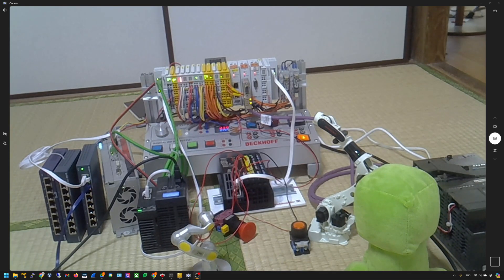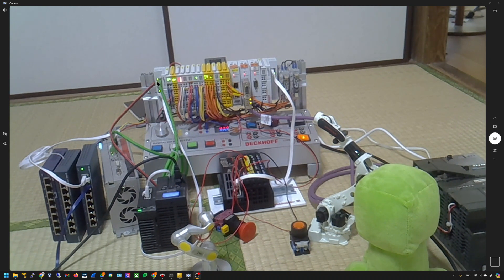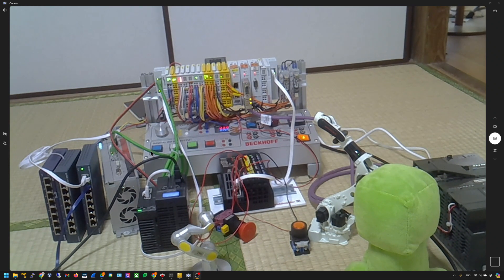Here is the real hardware configuration I'm using this time. The main part is the Beckhoff device — here is the EK1101 EtherCAT coupler. You can see a white cable connecting to my KEYENCE PLC KV-8000, and next to the KV-8000 there is the KEYENCE module KV-XLE02 — this is the module I'm using this time. It will act as the EtherCAT slave, which is why the white cable connects to this module. On the other side, the Beckhoff IPC has a green cable connecting to the EtherCAT coupler, and another cable goes to the network switch, which connects directly to my PC. A USB cable is also connected to my PC for KV-Studio.